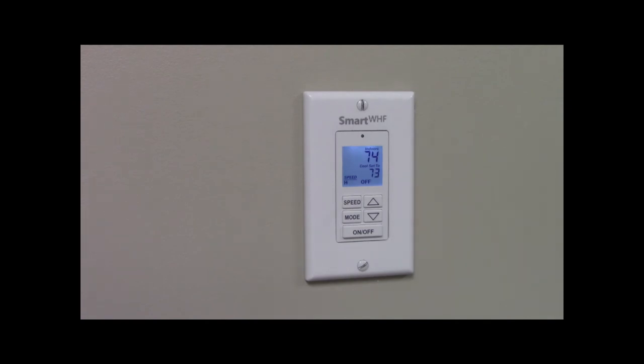3-speed and 1-speed fans will need to change the type of fan. Press and hold mode key for about 7 seconds until S timer is displayed. Press mode again to display the number of speeds. Press the up key to select a 3-speed fan or press the down key to select a 1-speed fan.